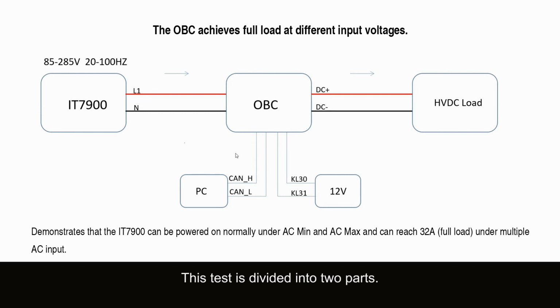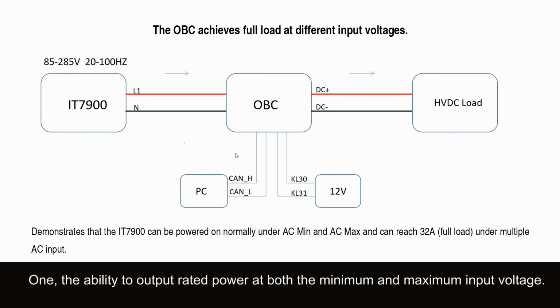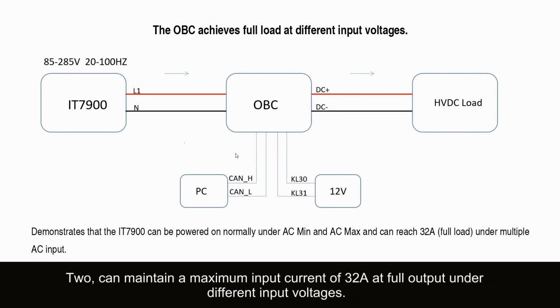The OBC achieves full load at different input voltages. This test is divided into two parts. 1. The ability to output rated power at both the minimum and maximum input voltage. 2. Can maintain a maximum input current of 32A at full output under different input voltages.